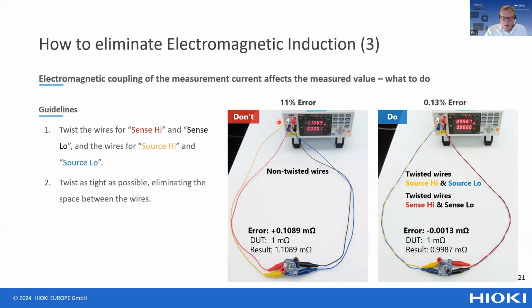The test current flows through the source high wire, the yellow one, and back to the battery tester through the blue source low wire. This creates an area in which there is a magnetic field, and this field is picked up by the wires of the sense circuit: the sense high, the red one, and the sense low, the black wire.